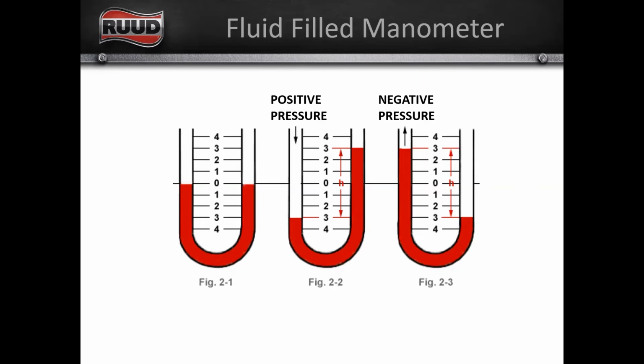So this inches water column, we've got figure 2-1, 2-2, and 2-3. Figure 2-1 would be a fluid filled manometer. It doesn't have its ports hooked up to any ductwork. It's just at regular atmospheric pressure, and the red U there at 0 on both sides represents the fluid in this water filled manometer. You can see it's zeroed out, and we don't have any pressure higher than atmospheric pressure on either the positive or the negative side.